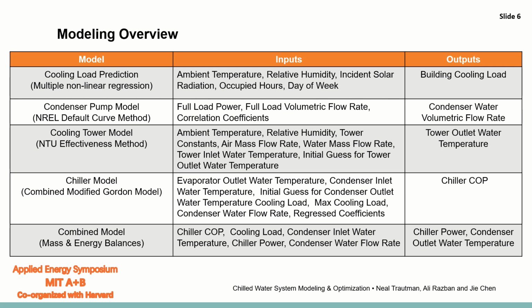Here in this table, you can see an overview of our modeling process. For our cooling load prediction algorithm, we used a multiple nonlinear regression algorithm to predict the building's cooling load subject to a variety of ambient and occupancy related variables. For our condenser pump model, we used the NREL default curve method. For the cooling tower model, we used the NTU effectiveness method. For our chiller model, we developed a modification that combines the Gordon model, which combines 2 different modifications, in order to incorporate condenser water flow rate as an input. And finally, we used principles of mass and energy balance to help link these models together and model the system as a whole.